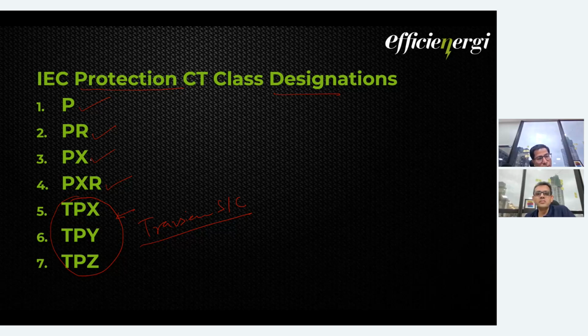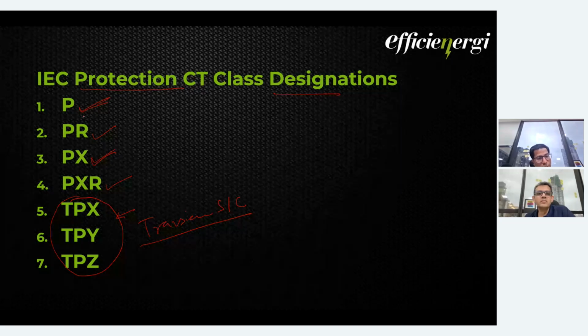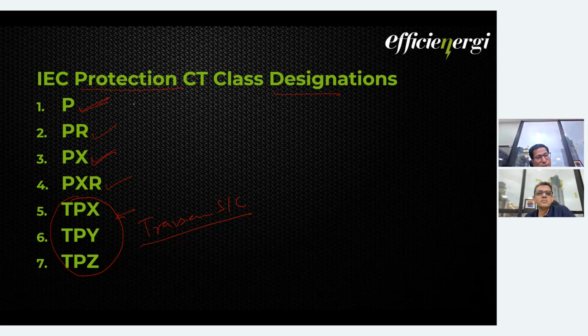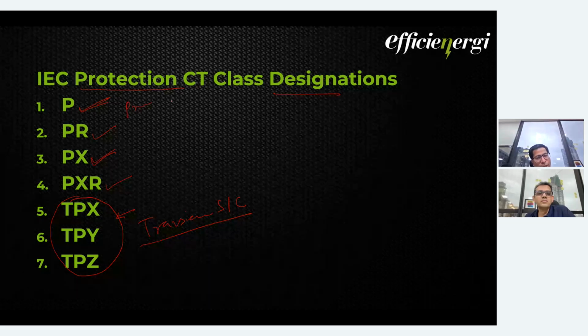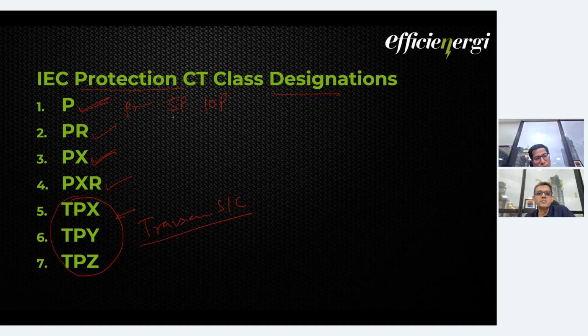The PX and PR, I just have a short explanation on this. P basically means a protection CT, wherein 5P or 10P is the class that we normally see. After that you have 10, 20, even 30, and in some cases even 40 is possible. So 40 means that is the ALF, that is the accuracy limit factor. PR is somewhat the same, but here R is for remanence. So remanence is taken care of.